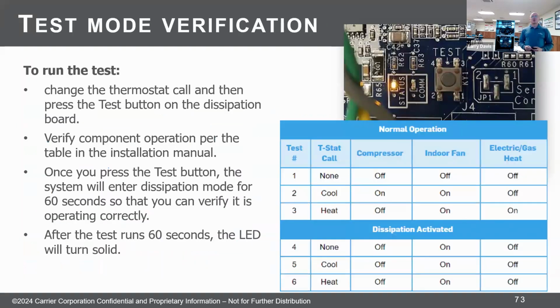Okay, so there is a test button. If you're out on just a routine maintenance on one of these systems, you can use that test button, and based on what call you're getting from the thermostat, the recommendation here is, if you're not calling, give it a call for cooling, give it a call for heating, and then press the test button and make sure it goes into that dissipation. It'll go into it for 60 seconds, and then the LED will go back to solid, and it'll run. What do you want to make sure it does? It stops your call. Does it make sure the fan is on? And does it go back out after the dissipation? Okay.